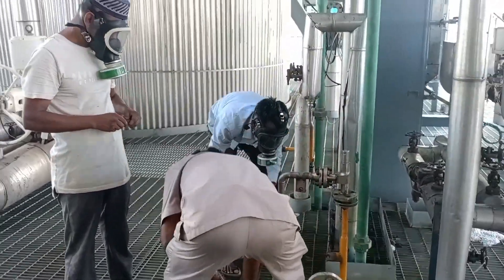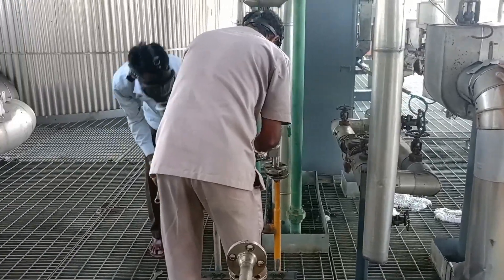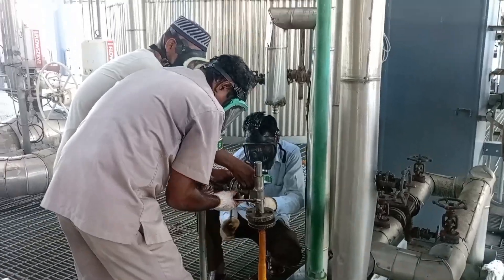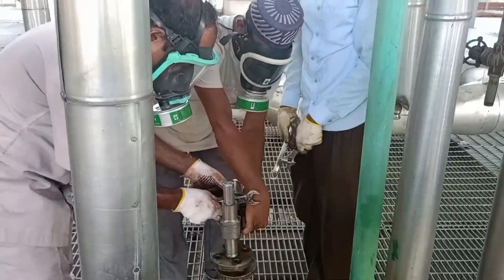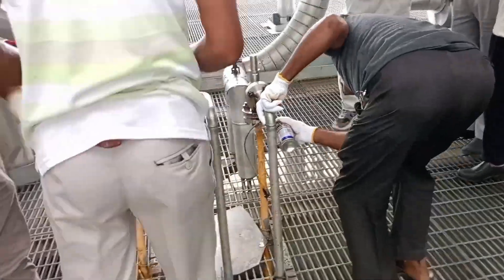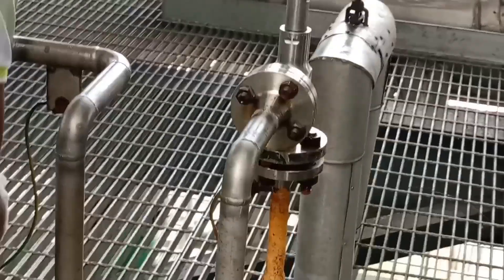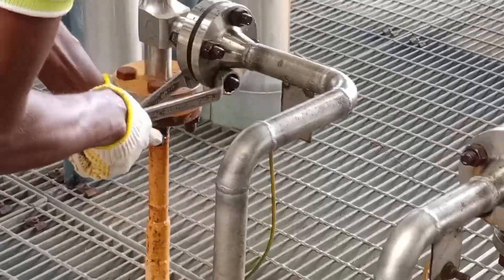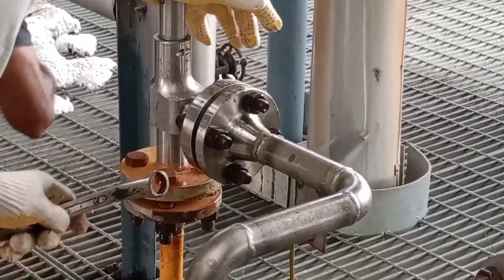We came to the decision to first check the PSVs, i.e., the pressure safety valves. To dismantle the pressure safety valves from the connected line, we maintained necessary safety. The suction line of the safety valve is connected to the high-pressure ammonia pump, which is a reciprocating pump. With a reciprocating pump, if the delivery valve is somehow closed, the pressure of the pump outlet line will exceed the delivery pressure.